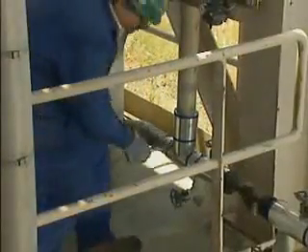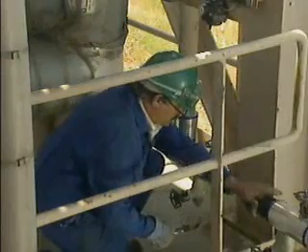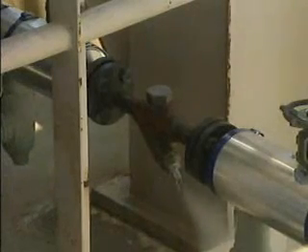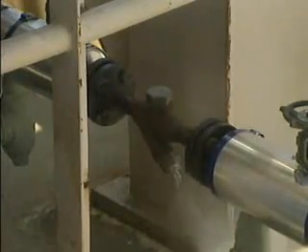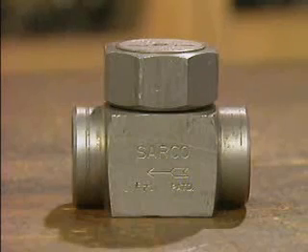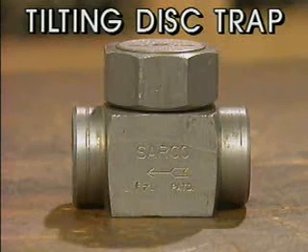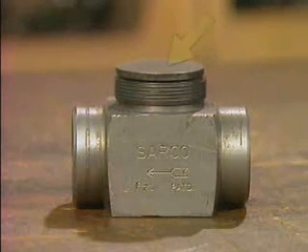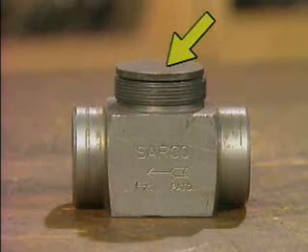A thermodynamic trap contains a component, such as a disc or a piston, that responds to variations in velocity and pressure related to changes in state of the incoming fluid. A typical disc type is the tilting disc trap, designed to handle low to medium condensate flow. The trap contains a disc—its only moving part—that lifts or tilts. At startup, the disc rests on seating surfaces that contact the trap's inlet and outlet, keeping the trap closed.